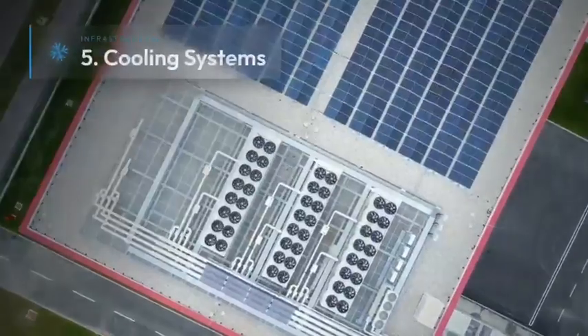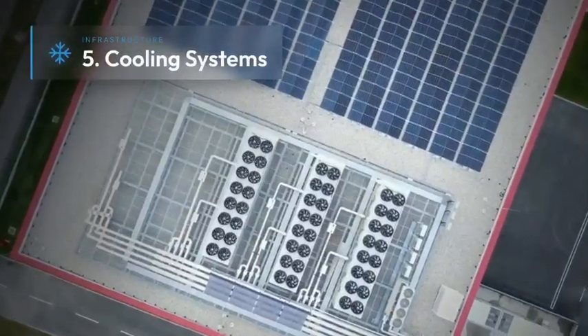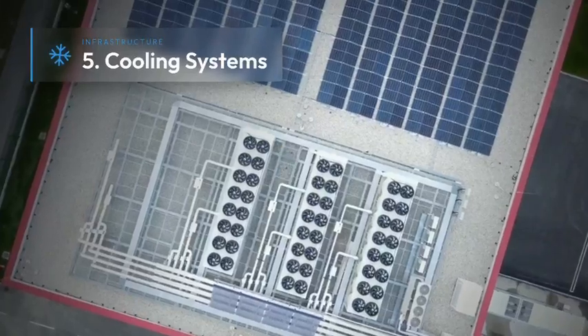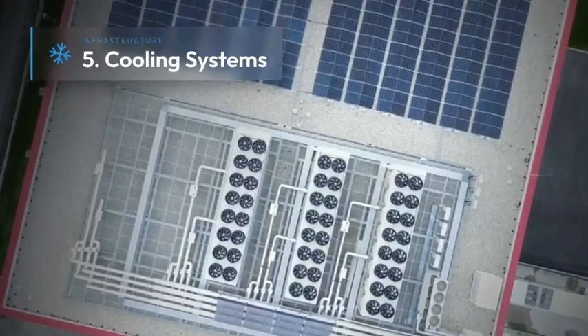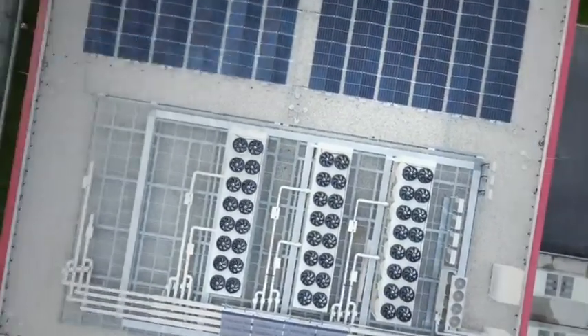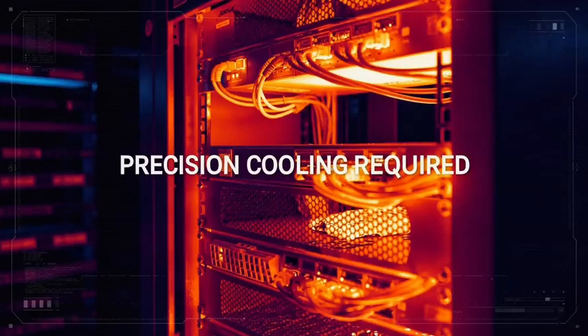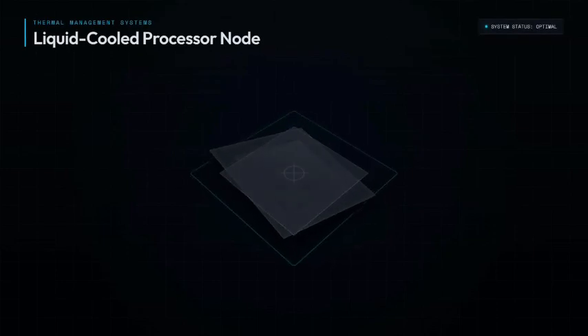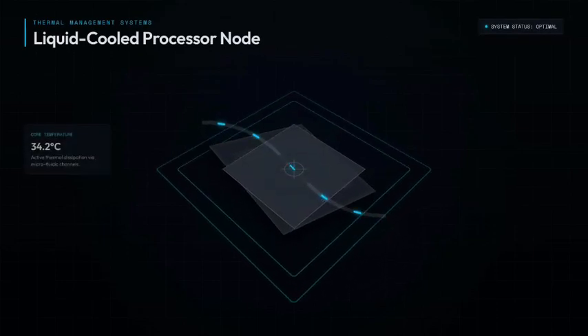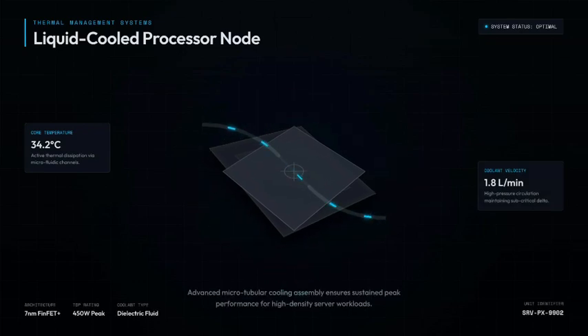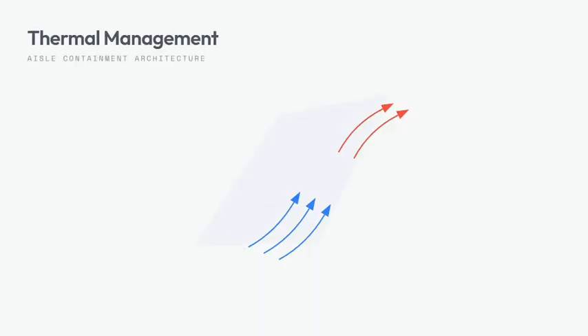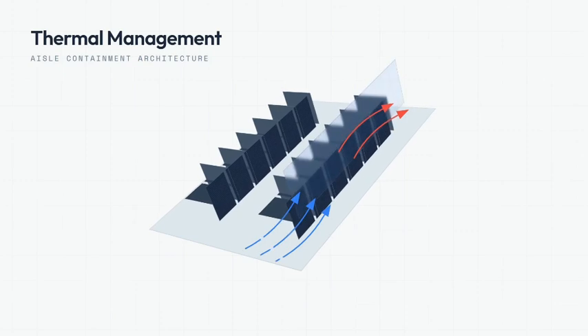Step 5, cooling. And this might be the unsung hero of the whole building. Every watt a server draws comes right back out as heat. Leave a room full of servers alone and it would cook itself in minutes. So data centers use precision cooling, CRAC and CRAH units, chilled water loops, and increasingly liquid piped directly to the chip. They also play a geometry game, hot aisles and cold aisles, physically contained so hot exhaust and cold intake never mix.